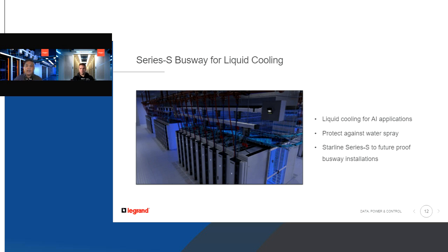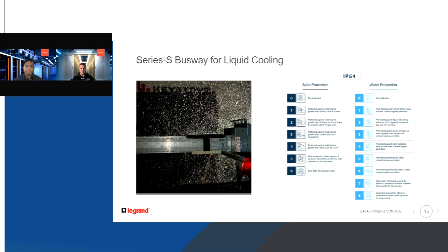The S-Series in itself is a splash-proof bus, and again, it is IP54 rated. That 5, if you're not familiar with the IP system, stands for solid protection, so it is dust resistant. But the main intent of the IP54 bus in the data center space is the water protection, and it has a level of protection of 4, which is splash-proof. The left image is one of the tests that we ran with respect to the water spray, and happy to say we passed that test.